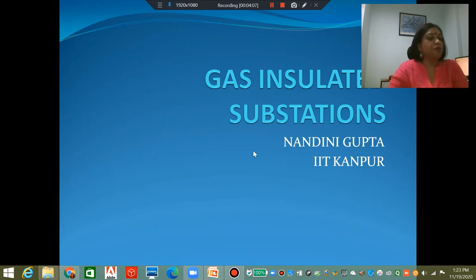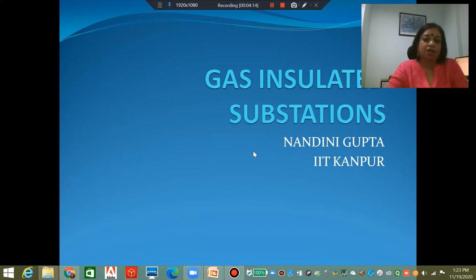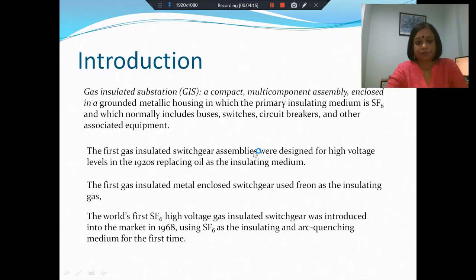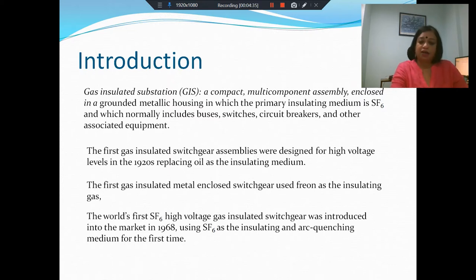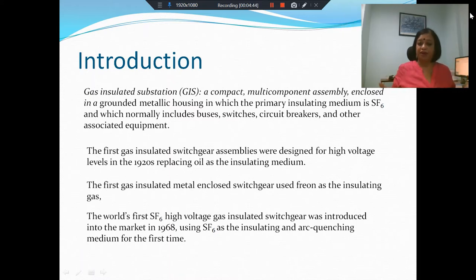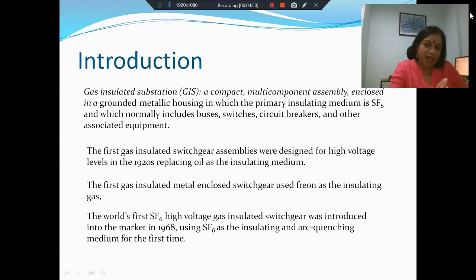So that means it is more expensive, of course, but we will see what gas insulated substations entail. When we talk about gas insulated substations, we are talking about a compact multicomponent assembly enclosed in a grounded metallic housing. The primary insulating medium is SF6, or sulfur hexafluoride. The assembly inside includes buses, switches, circuit breakers, and other associated equipment — the entire paraphernalia is housed inside the enclosure, which is filled with SF6 to provide insulation.